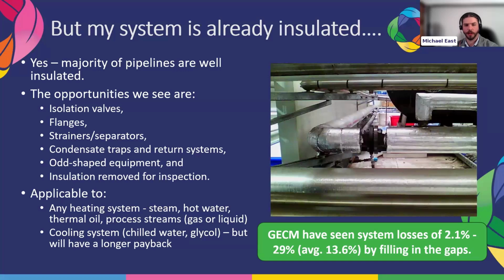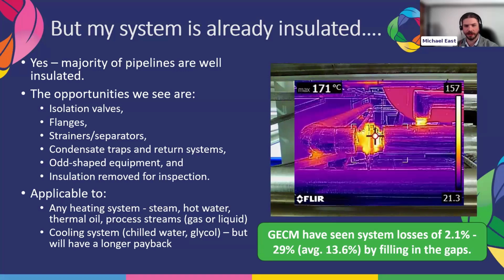Another good example of well-insulated piping, but we've got our friend here, the common flange in the middle, sitting at 171 degrees. So these gaps in the insulation - people think they've ticked off the insulation box. We did it years ago, it's done and dusted, no need to address it again. What we've seen is that anywhere between about 2% and up to 30% of the system's thermal losses come from these gaps in the insulation, and the average is about 13-14%.